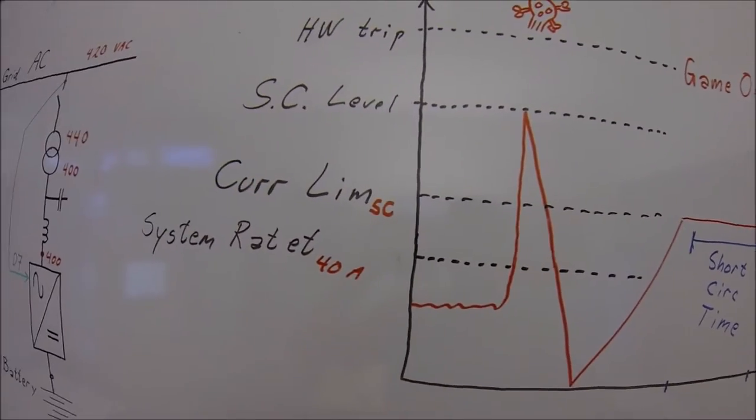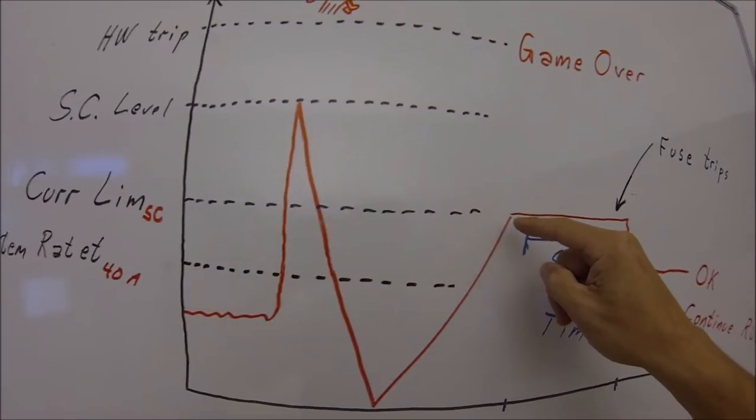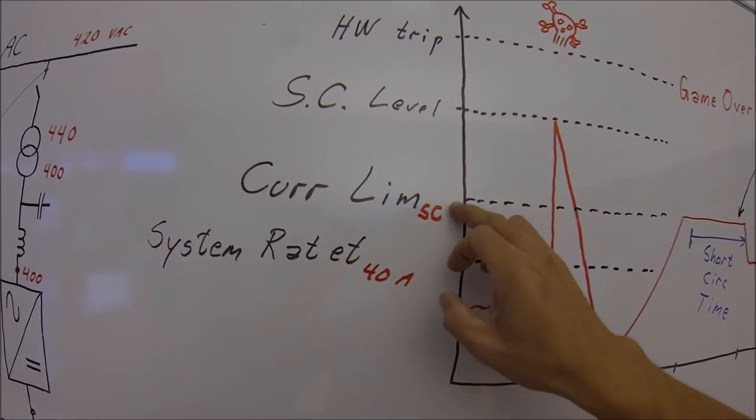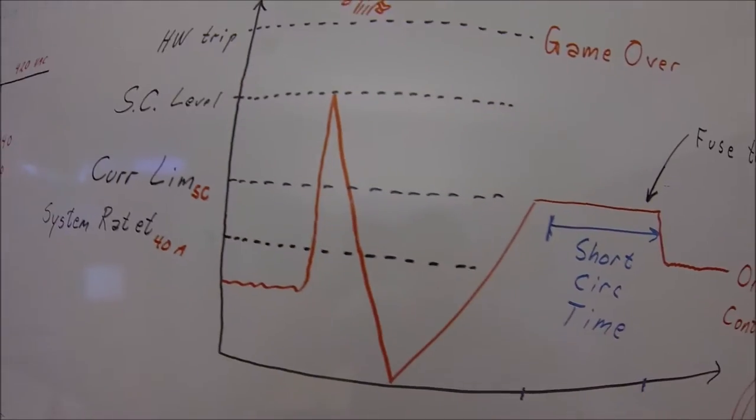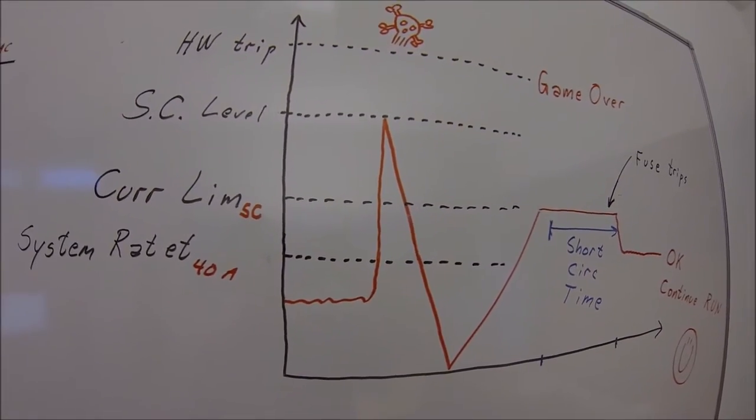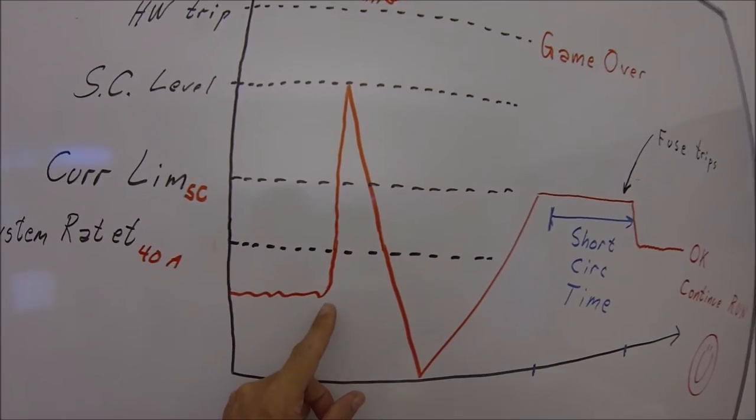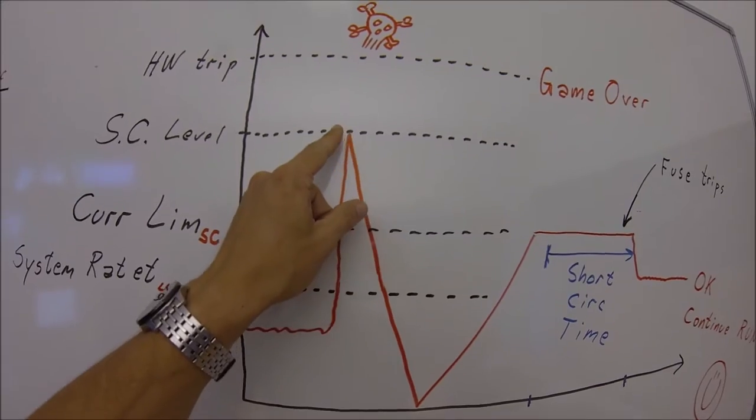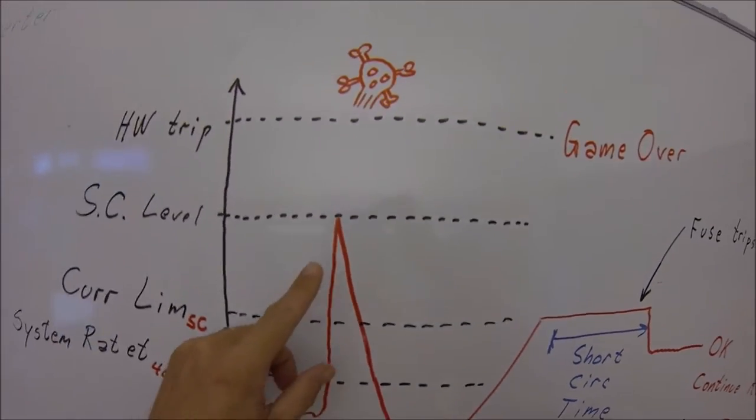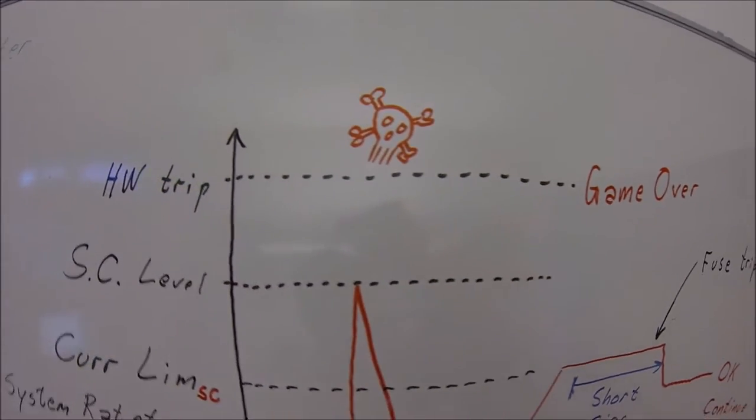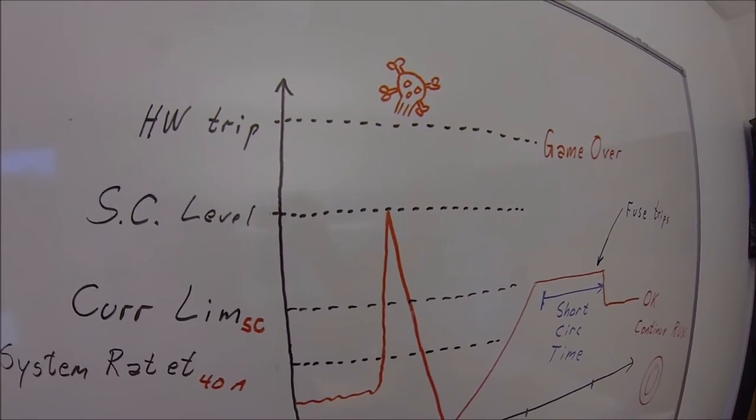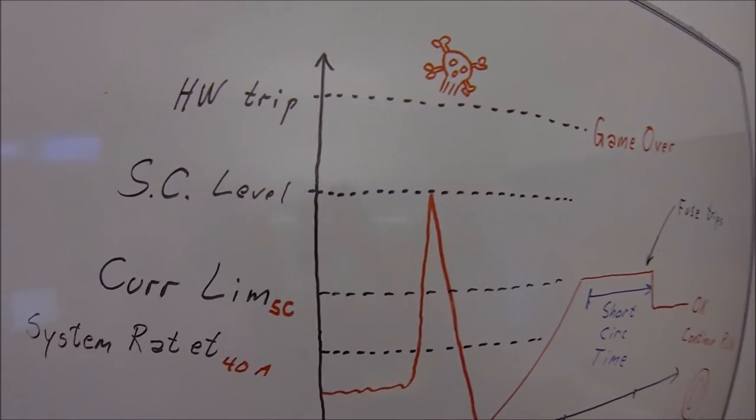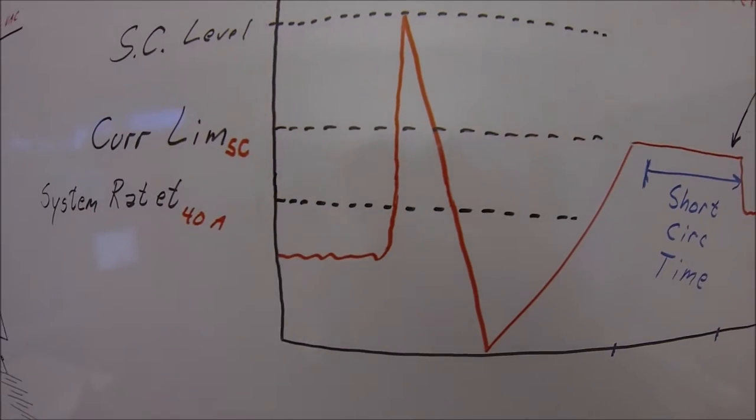The frequency converter has a current limit for short circuit. In the tables for this product I will find that some 85 ampere is possible to supply during a very short time during a short circuit. What happens if the short circuit brings the current a lot higher? Well if it reaches the hardware level there will be hardware circuits in a frequency converter cutting off the IGBTs and tripping, stopping the frequency converter. It stops totally and the grid we supplied is dead.